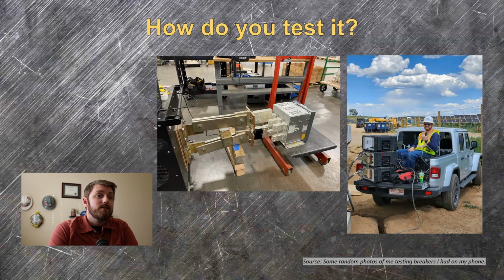Large power circuit breakers need to work. We prove that they work by using a high current test set and dumping a ton of current through them with a primary injection test set. We actually make the thing function how it will in the event of a fault. Similarly, if a facility is relying on maintenance mode system, we need to prove that works too. The team coming out to perform the breaker testing must fire up the maintenance mode system and verify that it works. Here's a couple ways to make sure that it's working during testing.